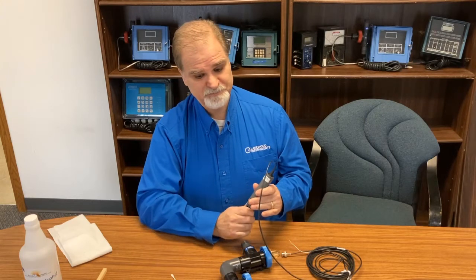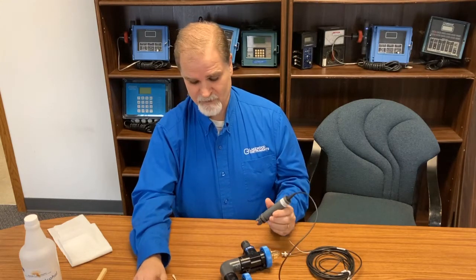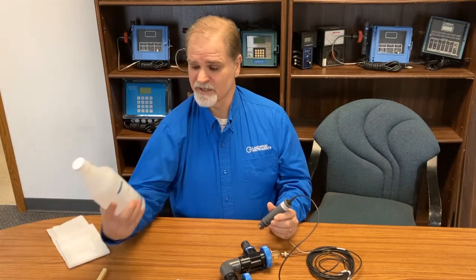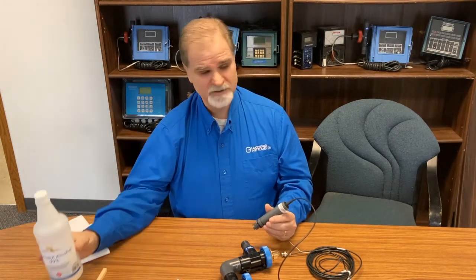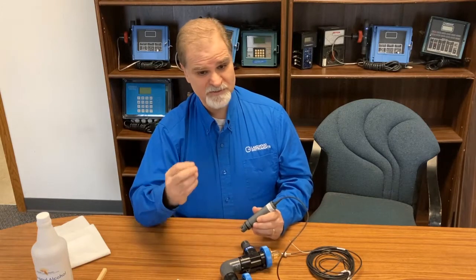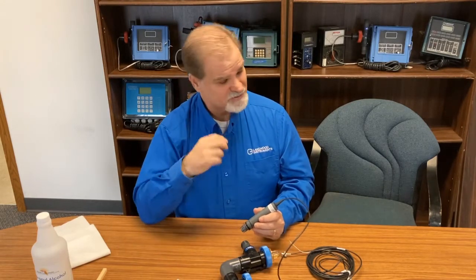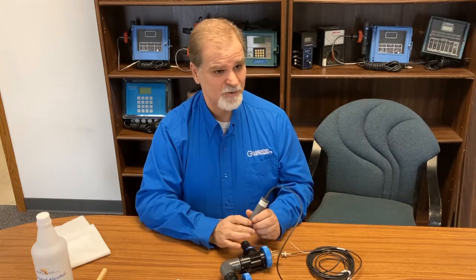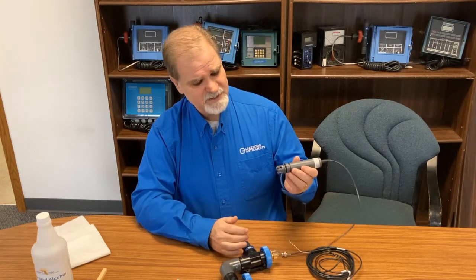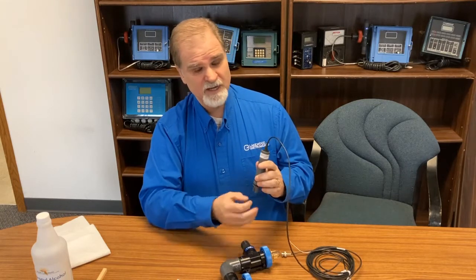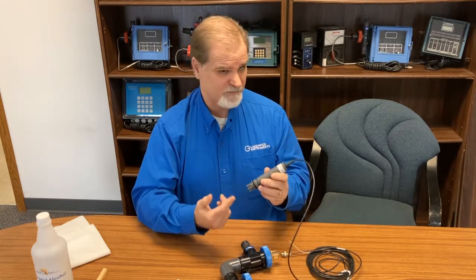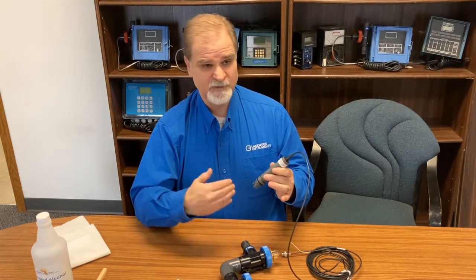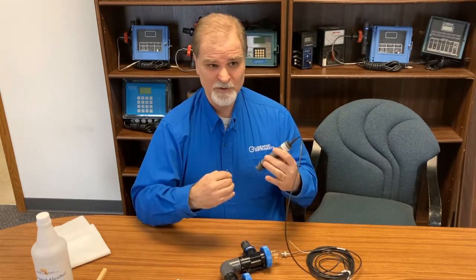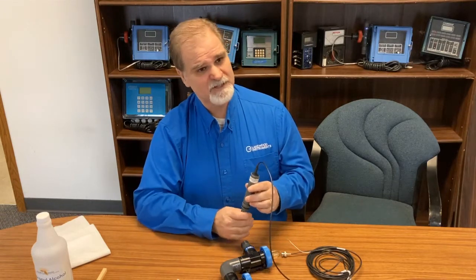If you're worried about oil getting on the surface of the sensor, is IPA, or isopropyl alcohol, still the right thing to use to clean it up? Yes, it is. We use 99% or 91%, which will work just fine to clean those films off. Now remember, you still have to remove the source of those oils, or as soon as you put it back in the system, it's going to coat that probe and affect the reading. These sensor tips are designed to be in direct contact with the water, and if they have any kind of coating on the glass or reference junction or solution ground, they will cause the reading to either be high or low or not respond at all, have very limited response.